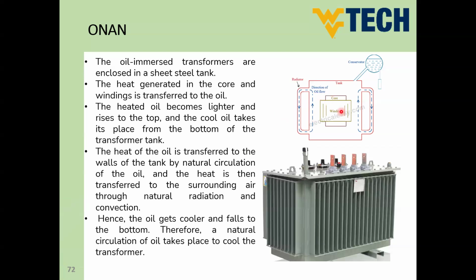So here is our core and windings inside the big tank, and the tank has these radiators here to make circulation for the oil. Since the heat is going to be transferred to the oil, the cold oil will go down and the hot oil will go to the top, and then the hot oil will be circulated inside the radiators here, which have contact with the air outside.